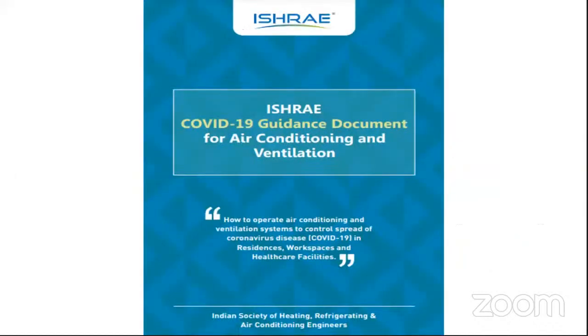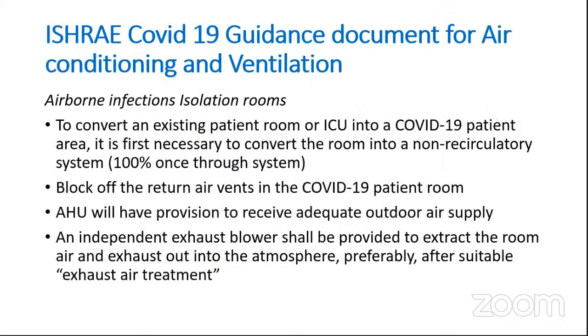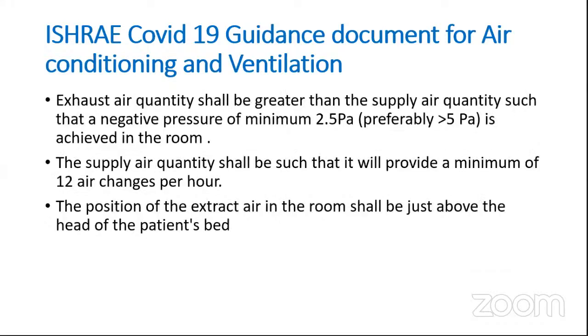Now, this is something which I think most of you must be aware of, but still I thought I would highlight some points which are very important and very easy to understand when we talk about air conditioning and ventilation in COVID patients' rooms. If we are talking about an airborne infection isolation room, an existing room can be converted if we cut down any kind of recirculation in that system. We need to block off the return air vents in the COVID-19 patient room. There should be adequate outdoor air supply from the AHUs. An independent exhaust blower can be provided to keep the pressure differential in that room.